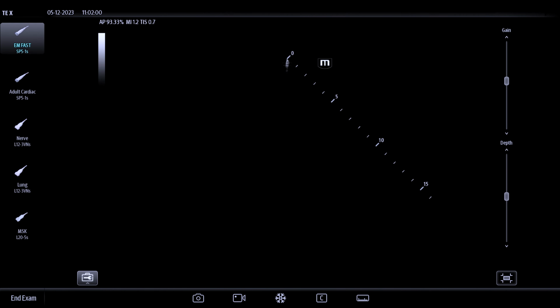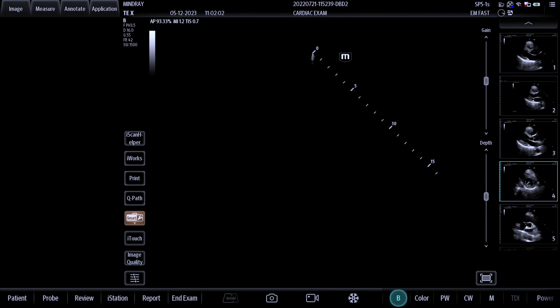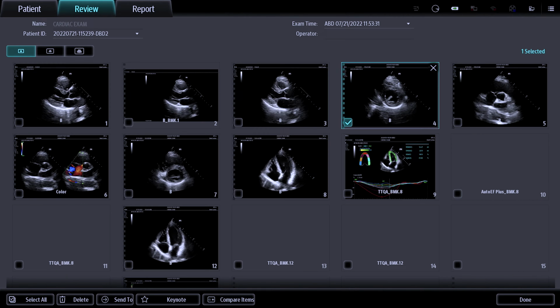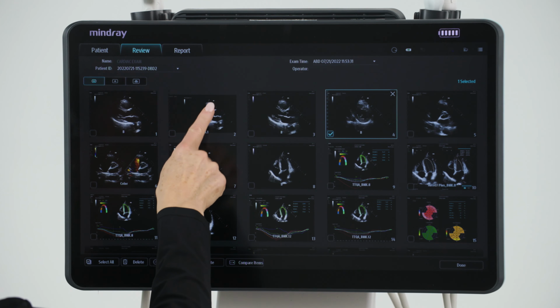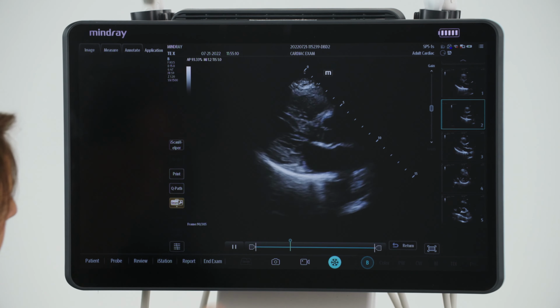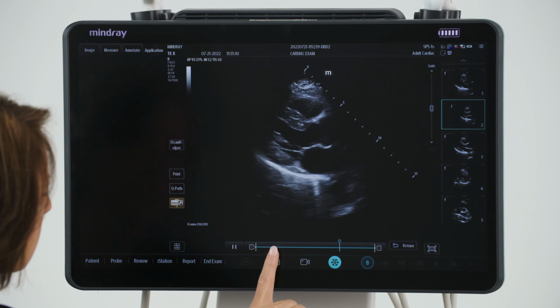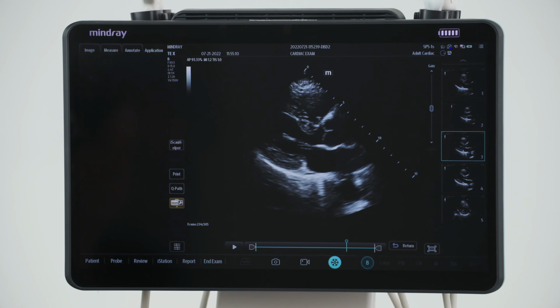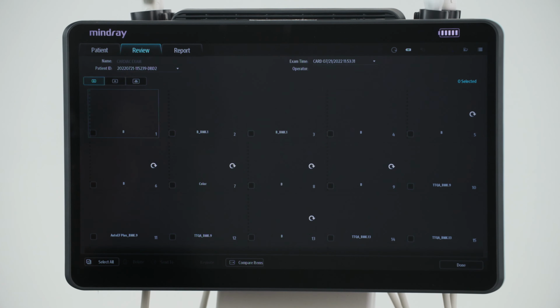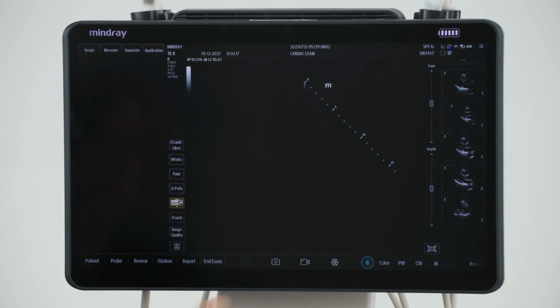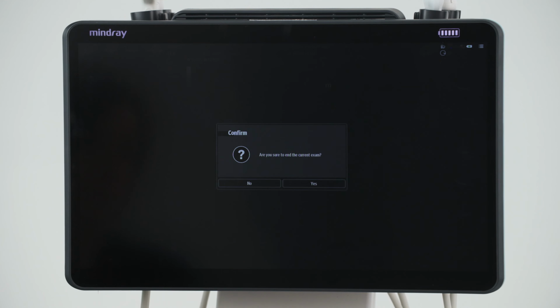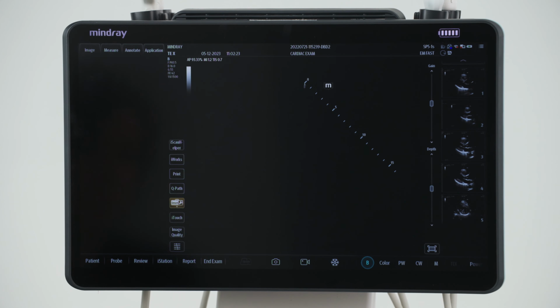Post-processing features are available, such as adding annotations or measurements during review as well. An edited image should be saved and will display right after the original one on the review screen. Once all necessary changes have been made, select Done to exit review mode and return to the main imaging screen. Select End Exam. If the system will be transmitting images to a PACS, an application specialist can set up the system to automatically transmit images when selecting End Exam if desired.